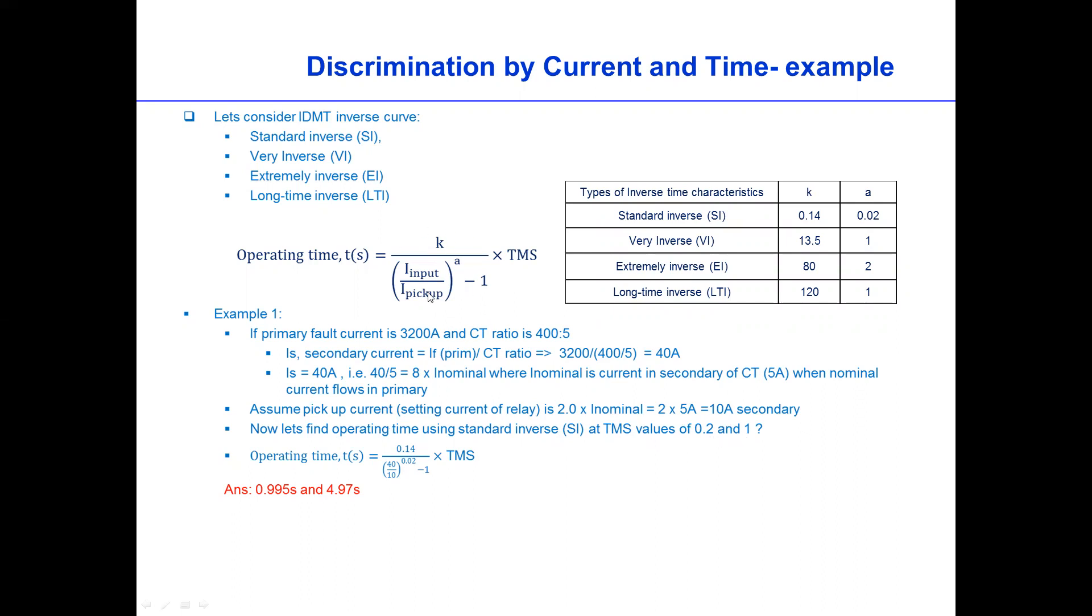So we can just use this equation and plug in the values, the input current of the secondary value is 40, the setting current is 10. And then if we put TMS 0.2, then the trip time will be 0.99, which is one second. And then if we put the TMS value is 1, then this will be 4.97 seconds.